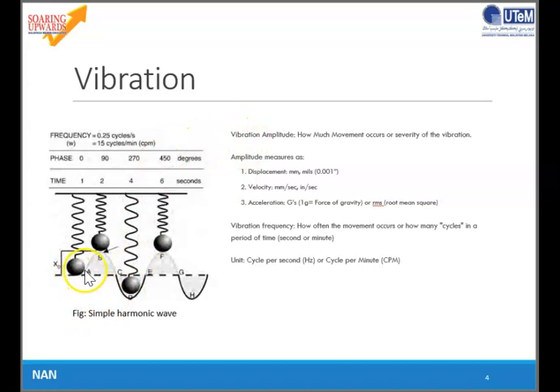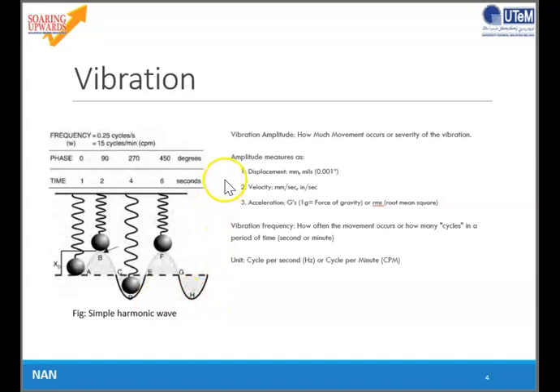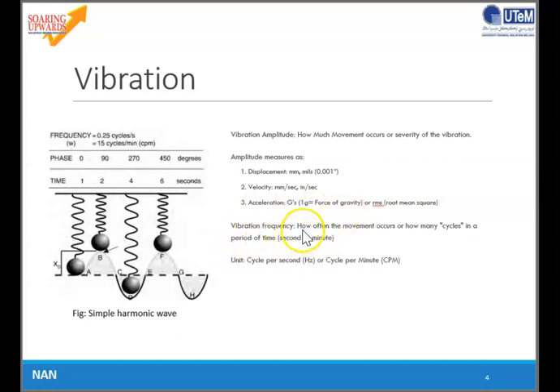This slide shows a simple harmonic wave with points A through H, and we can measure time and also phase. During measurement, there are three types of amplitude measurement: displacement, measured in millimetres; velocity, measured in millimetres per second; and acceleration, measured in G or millimetres per second squared. Vibration frequency is how often the movement occurs, or how many cycles in a period of time, with units of hertz or cycles per minute.